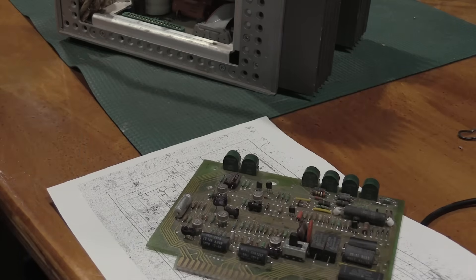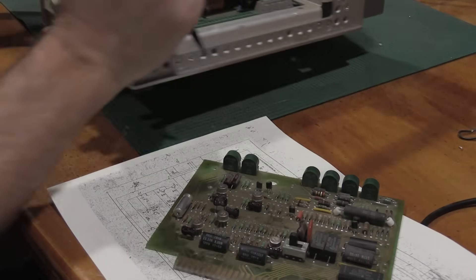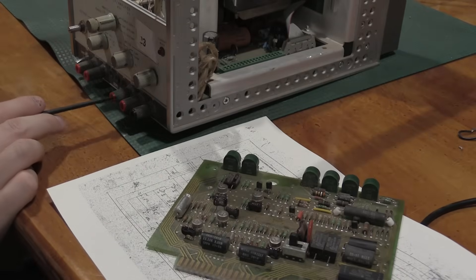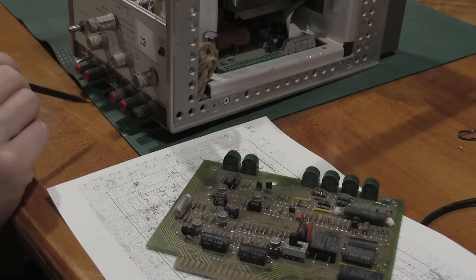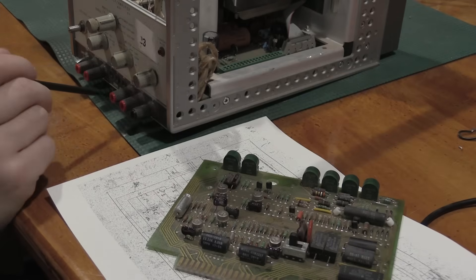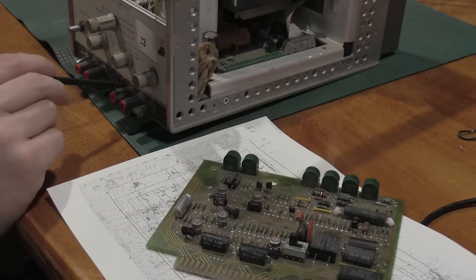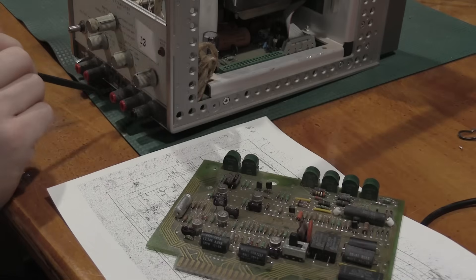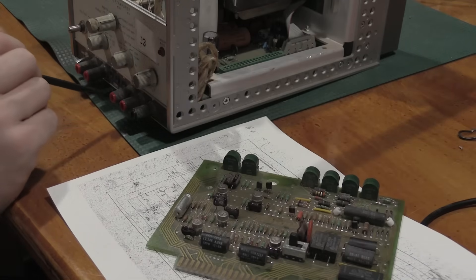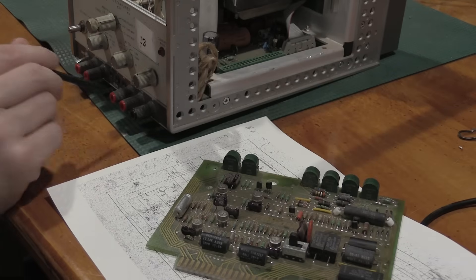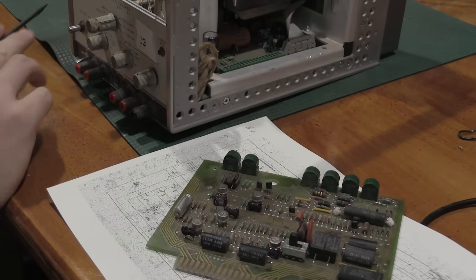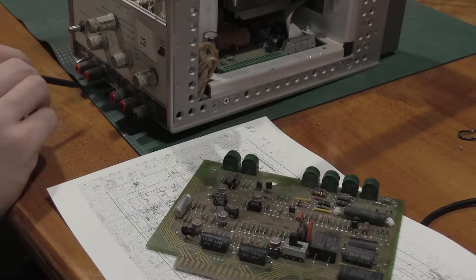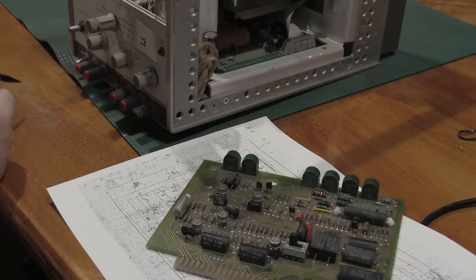The resistor that burned up, on the other hand, is part of the output. So the relay, when this unit's off, because this can source and sink current, so it needs to pull some in. So if you push current in, it's got to go somewhere. Well, the relay closes and puts that one-ohm resistor across this contact. So I have a sneaking suspicion is something was pushing into this thing, that relay closed, and that one-ohm resistor saw a ton of current for whatever was pushing into this thing, some form of power supply or battery or something like that. Reverse biased and burned up that resistor. So it's just a straight resistor across the contacts, that's what that relay does. And I think it just saw too much power and got super hot.